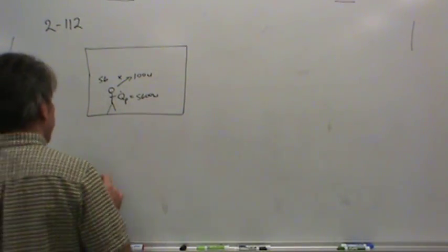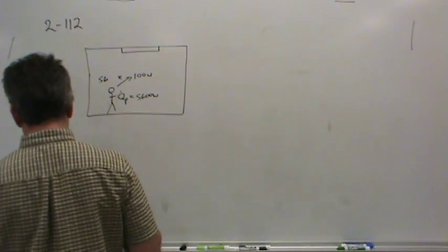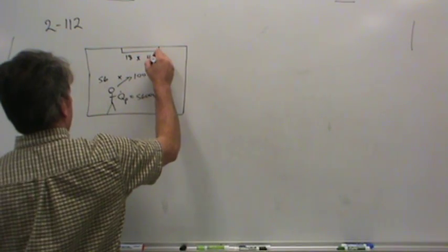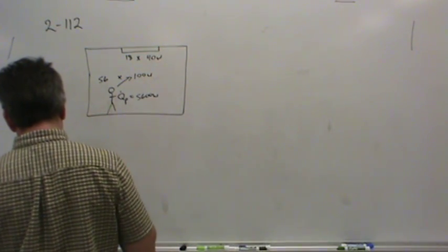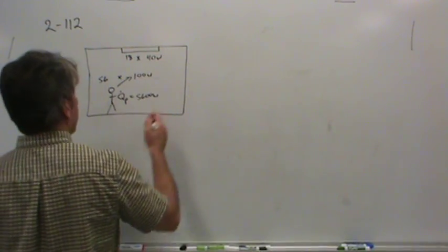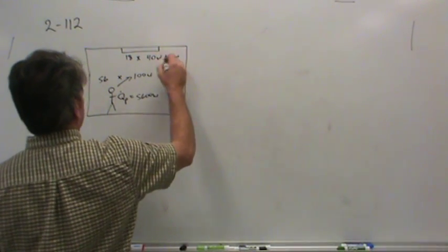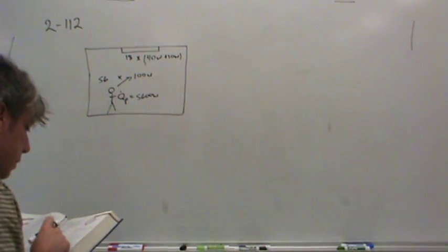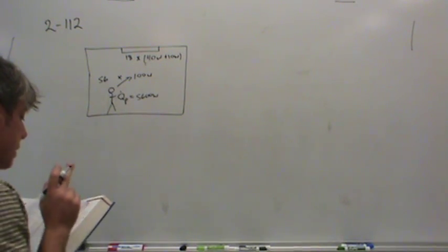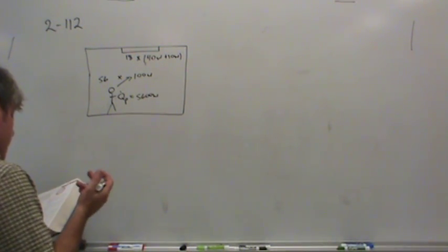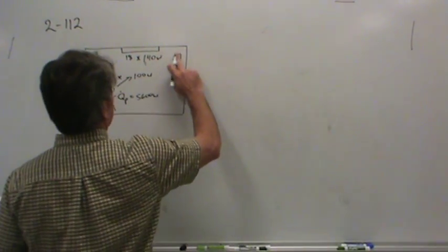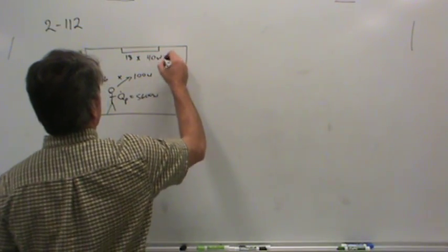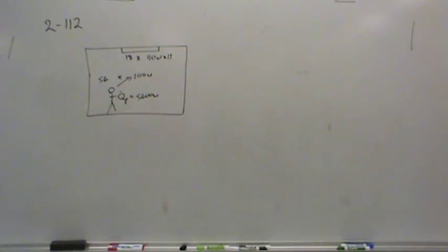Okay, the lighting is 19 fluorescent light bulbs. We've got 19, each at 40 watts, but the ballasts, which there's one ballast per bulb in this case apparently, is 10 watts. So really, those two things go together. Okay, make sure I got that right. No, I'm sorry, it's not 10 watts, it's an additional 10%. So basically what we have to do is multiply by 1.1. Okay, so there's our additional 10%.